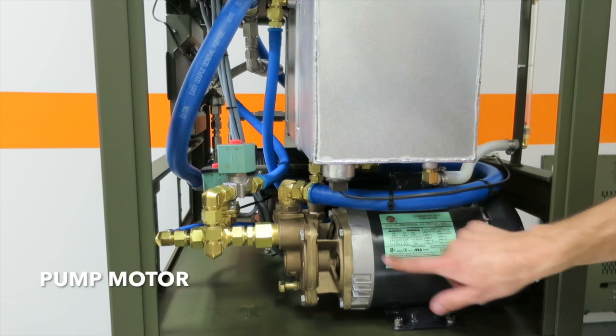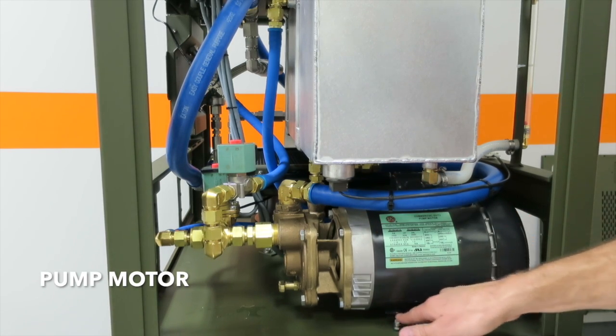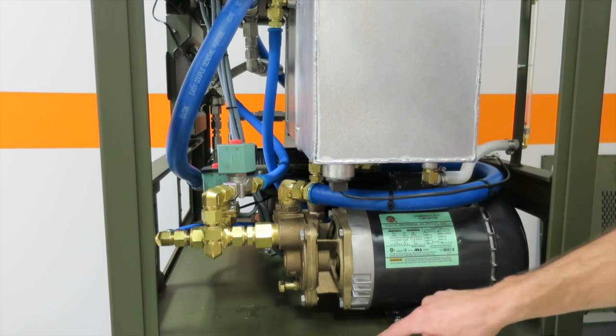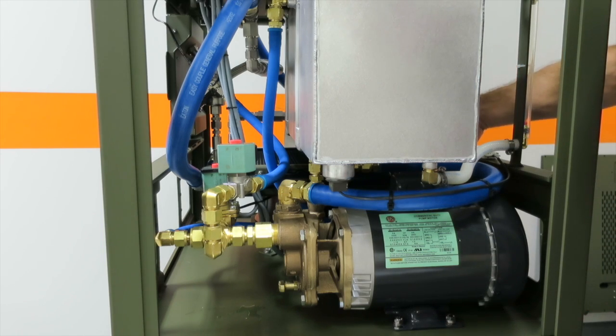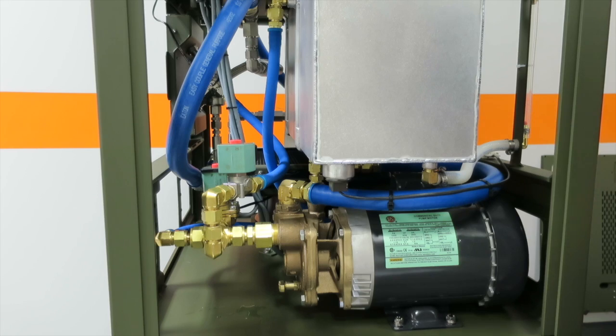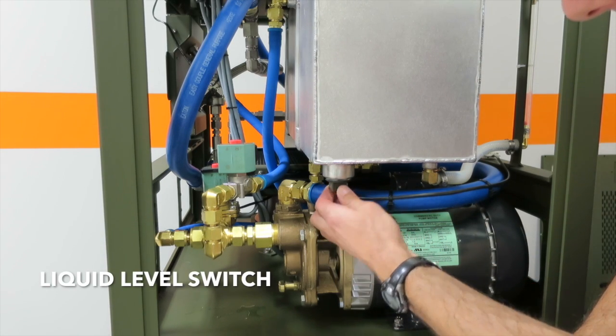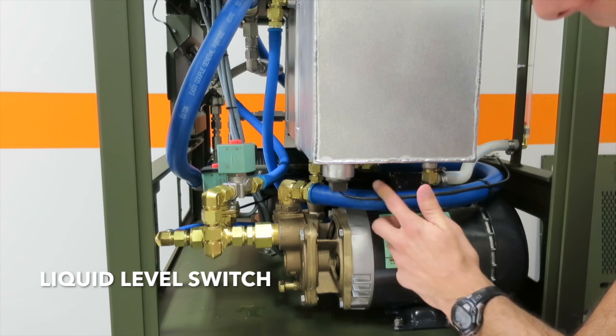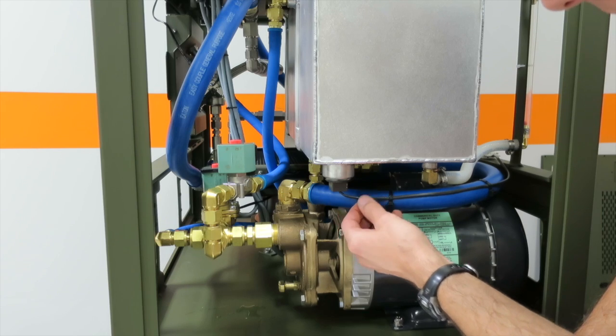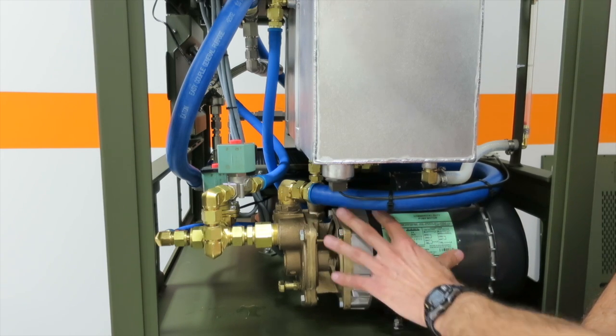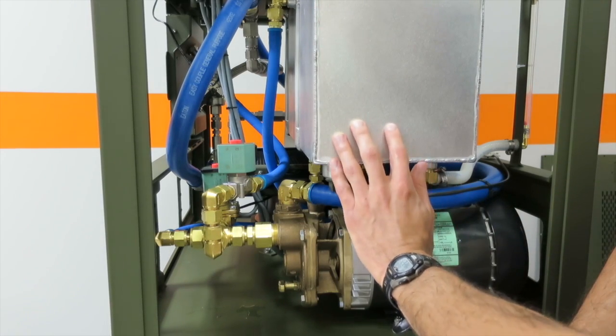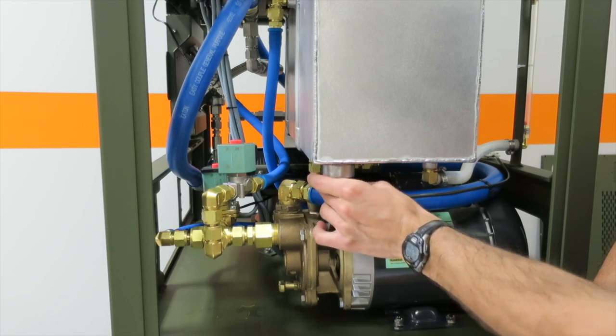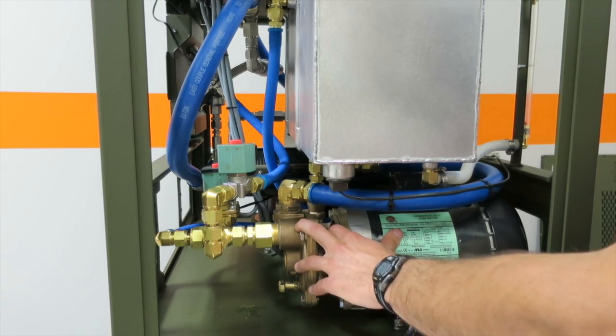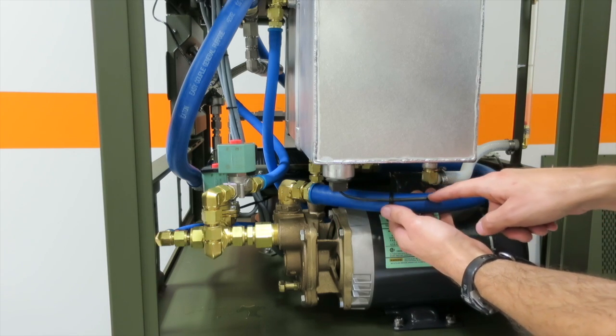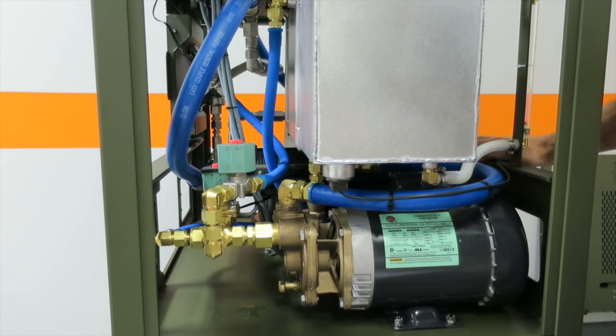Right here, we got the motor nameplate if you need any of that information off it. Got the mounting bolts down here that mount it to the base plate. And the wiring is actually on the back side of it, so you can't really see it from this angle. Right here we have the liquid level switch. This is an MPT fitting, so you can remove it with a crescent wrench if you ever have to replace it. The liquid level switch protects the motor and pump from running dry. If the water level ever drops too low, the liquid level switch will prevent the motor from turning the pump. And you can see the wiring route along the hose right here and go over to a connector and then is wired into the electrical box on top.